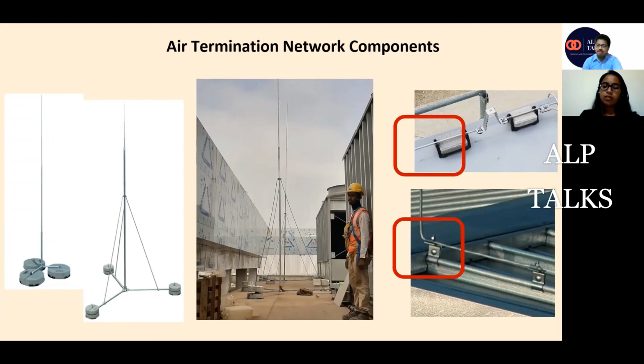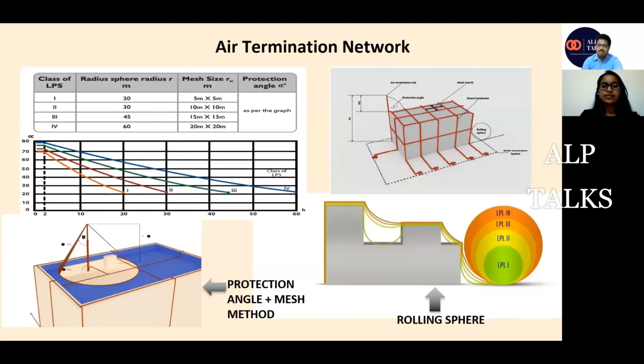So, the mesh method, how is it different? How do we do the mesh? Can you explain that one? As you can see in this image, a mesh is installed over the roof. The mesh size is given: for level 1 it is 5 by 5 meters, for level 2 it is 10 by 10 meters, for level 3 it is 15 by 15 meters, and for level 4 it is 20 by 20 meters.